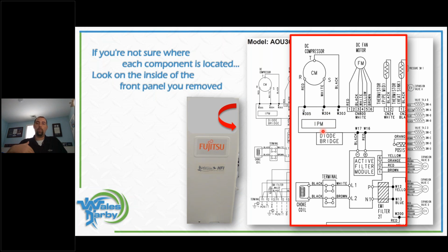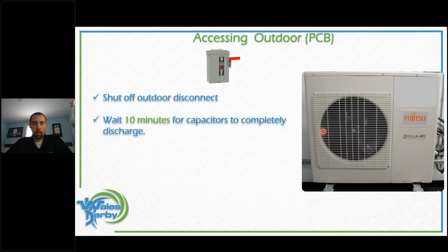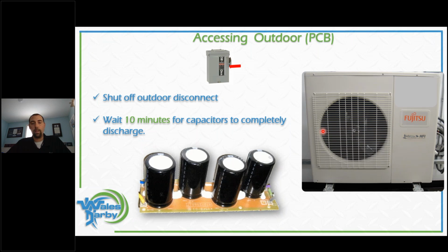So if you get comfortable with locating the parts and pieces, what they're called and where they're plugged in, that's going to cut down troubleshooting time by more than half, I would say. Anytime we're accessing the PCBs, or printed circuit boards, or any component that has electric going to it, we want to shut off that disconnect and wait 10 minutes for those capacitors to completely discharge. If you happen to be working in a quiet area, you might hear the click of the unit, the capacitors discharging themselves.